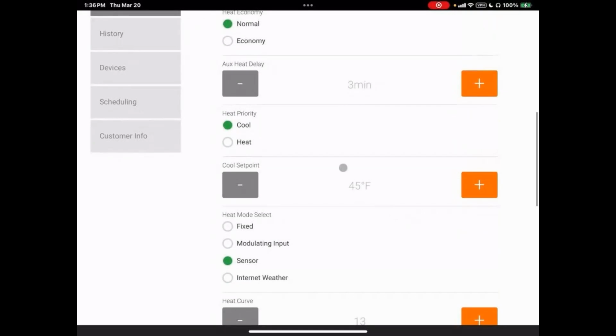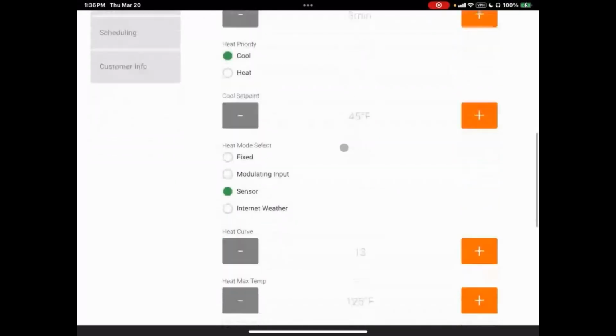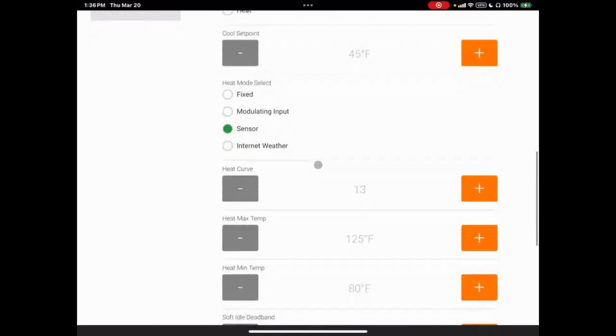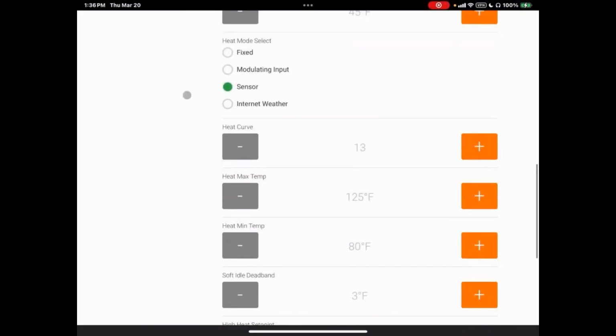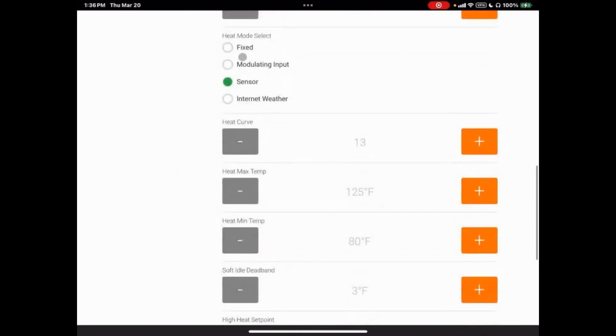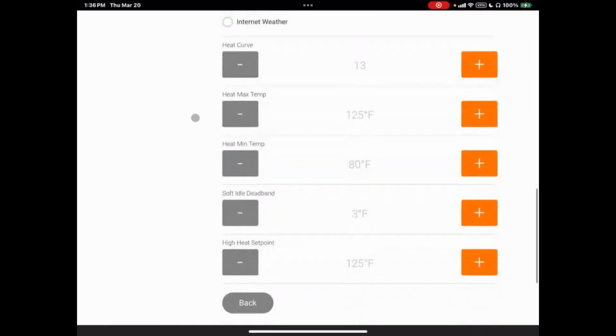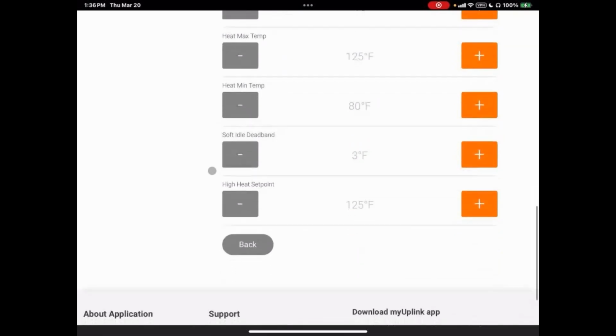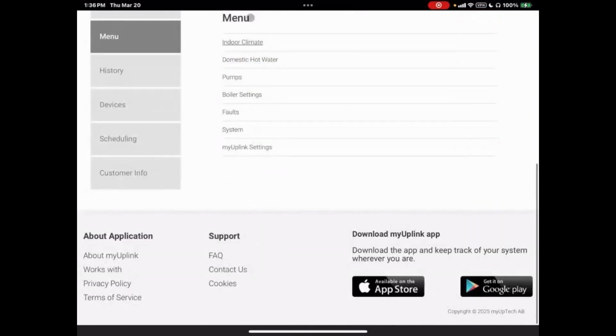I can set up these AUX heat delays, my cooling set point, and my heat mode. Here we have an outdoor air temperature sensor, but this is where you could change it to internet weather, put it in a fixed mode, or use the modulating input, which would be for cascading systems. Then we can select our heat curve and our minimum and maximum temperatures for the heat call. And then we have soft idle deadband and high heat set points. So a lot of information available here.